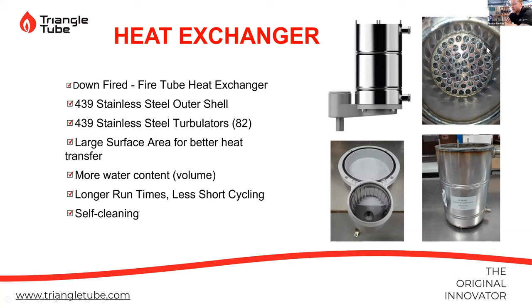With natural gas, these things run pretty darn clean. Natural gas is pretty clean if the burner and your combustion are set up properly. Propane tends to be a little bit dirtier. So on the service aspect, you're not getting in there every year to pull this burner and clean it. This unit 100% should be serviced and looked at every year. Your gas pressure should be checked, your combustion should be checked, but you're not necessarily pulling that burner every year. Most of the debris is going to be pulled down through the condensation, down through the bottom of our pan, and out through our condensate trap. So technically you could say it's self-cleaning, but there's still debris that can build up in here.